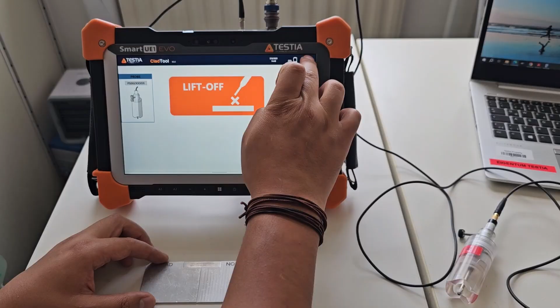Now let's go with the ultrasonic thickness gauge. This application is pretty useful because you have a small screen for checking and also for setting your parameters when you have to do a thickness measurement, like a grid measurement. We have, for example, an easy way to calibrate, only 2 steps. What we also like is that you can move the gates with your fingers. So it's pretty easy, not just pushing buttons, but using your fingers to move the gates.